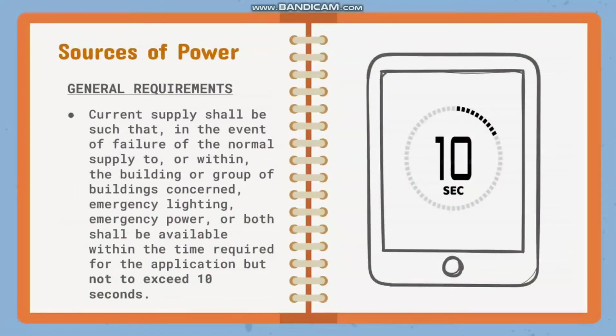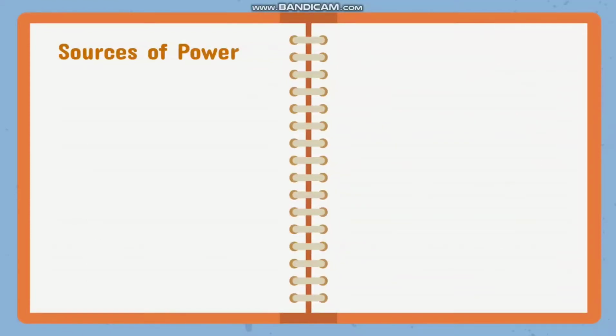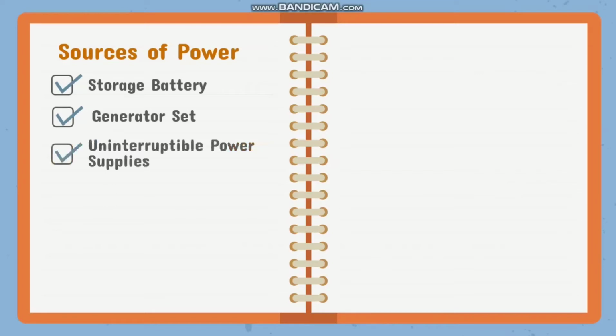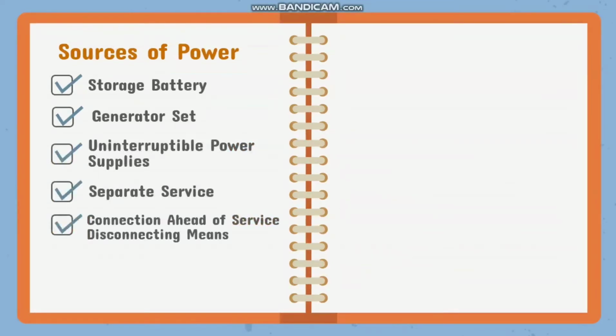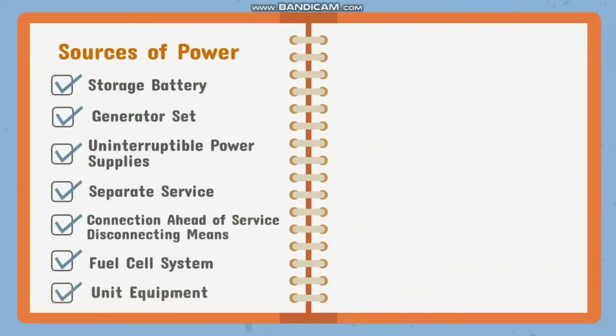Sources of power, general requirements. Current supply shall be such that in the event of failure of the normal supply to or within the building or group of buildings concerned, emergency lighting, emergency power, or both shall be available within the time required for the application but not to exceed 10 seconds. So, sources of power includes storage battery, generator set, uninterruptible power supplies, separate service, connection ahead of service disconnecting means, fuel cell system, and unit equipment.